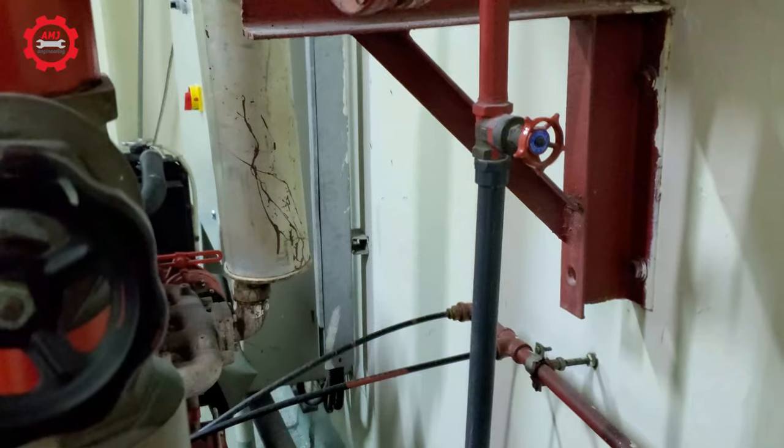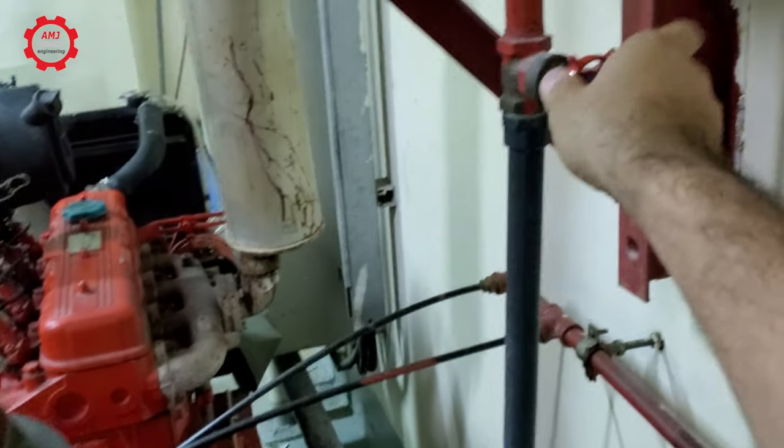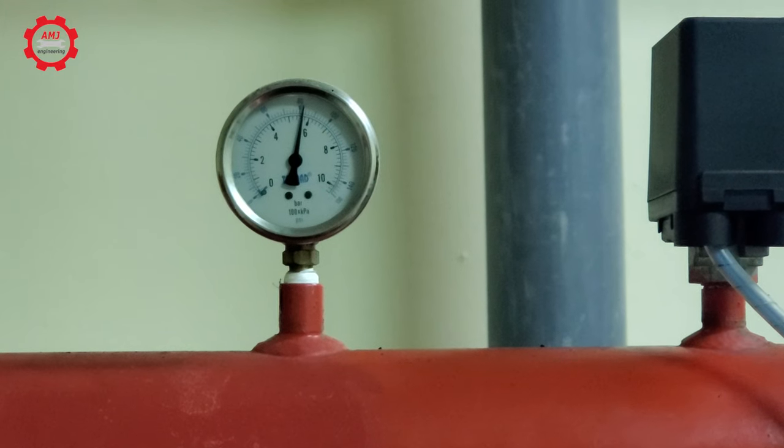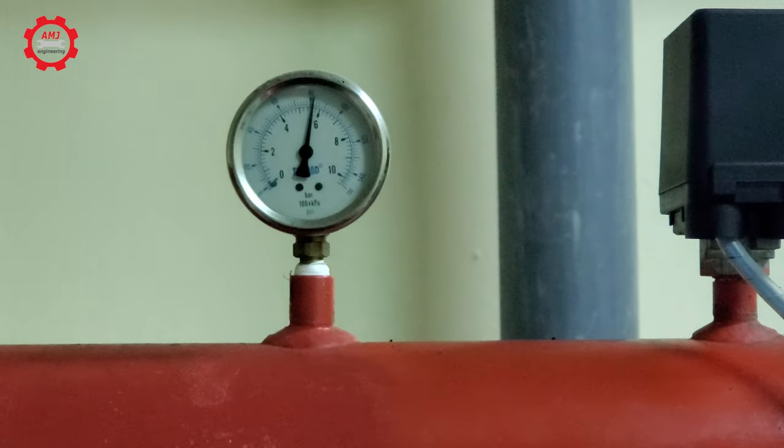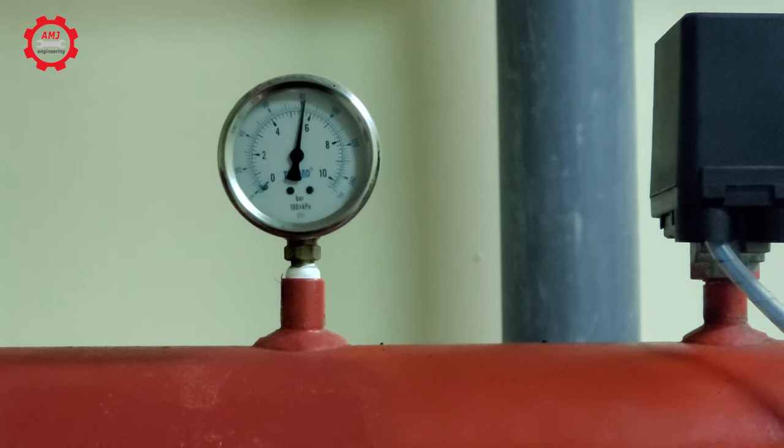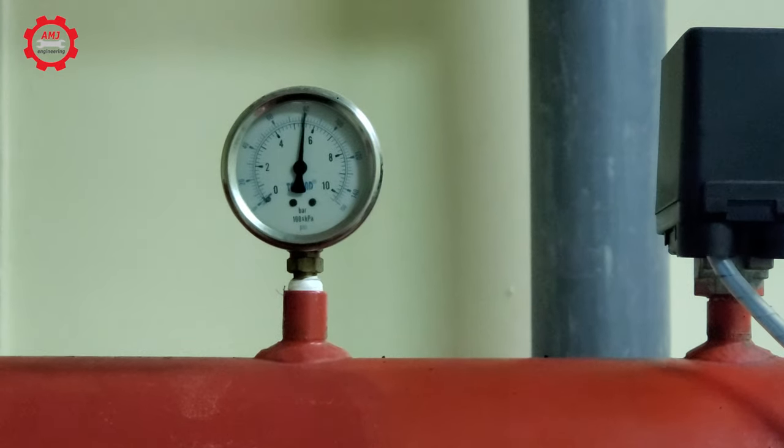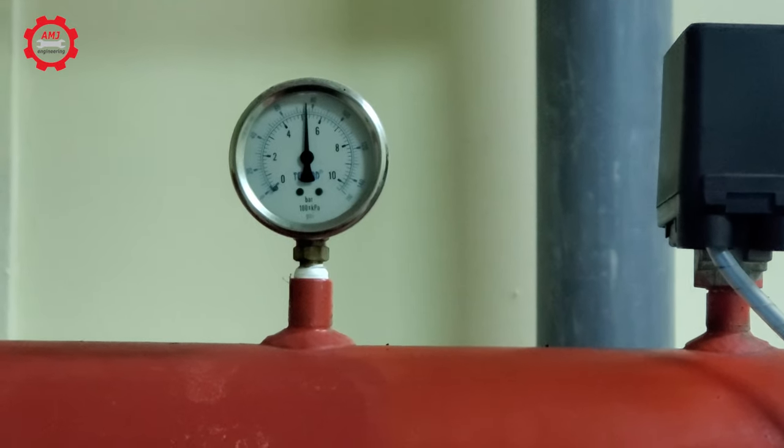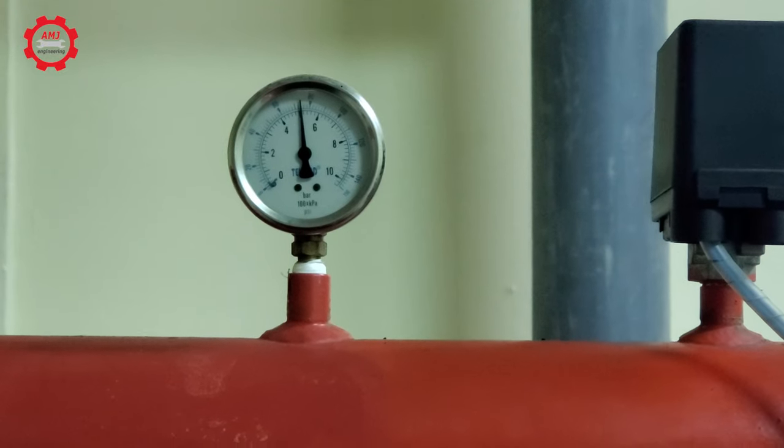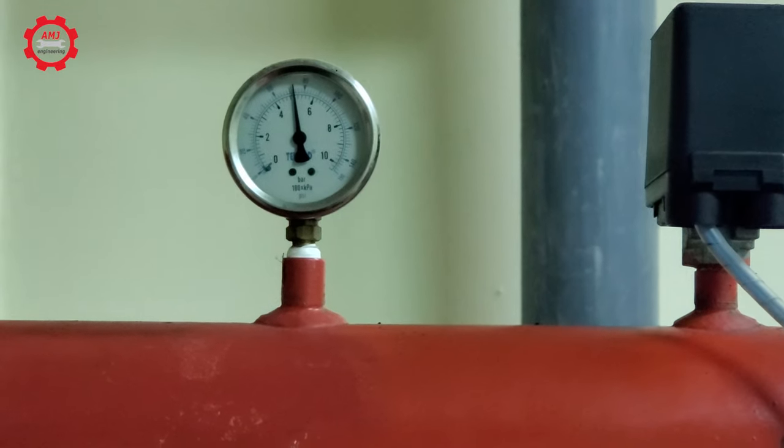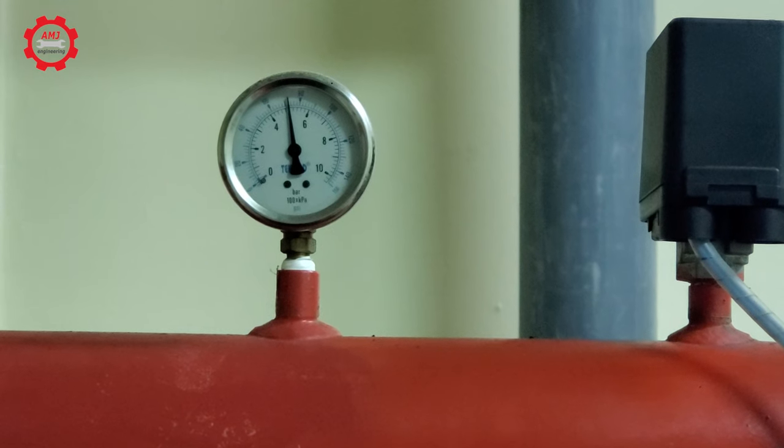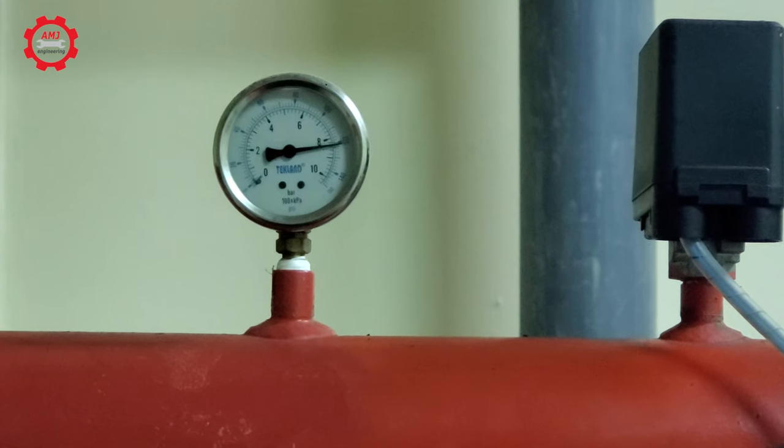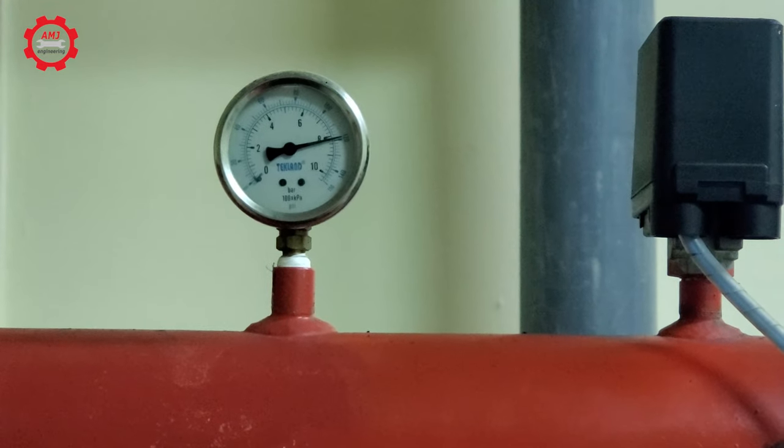I will open the test valve again and monitor what is going to happen. The pressure continues to drop beyond 5.3 bars as you can see, and no pump will start because the jockey pump controller is put on off position. When the pressure reached 5 bars, the preset cut on pressure of the main pump, the main pump starts automatically and stops automatically at the cut off pressure settings.